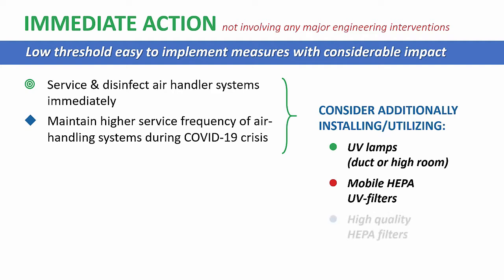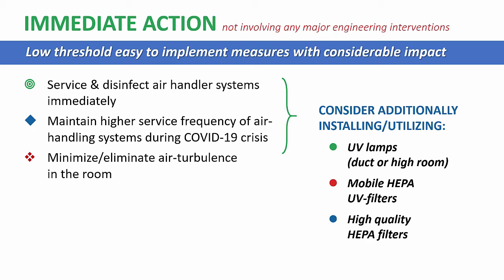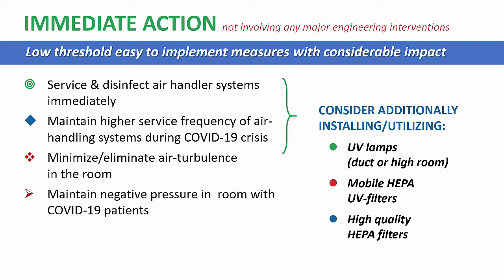And we can also install high quality HEPA filters. These filters we normally install in the supply grills or in the supply duct, to avoid particles to come into the conditioned space. And we can also install them in the return duct to avoid contamination, viruses, bacteria, dust from the living space to go to the air handler again. Another important thing is in rooms with COVID-19 patients to create a laminar flow in the rooms and avoid turbulence as much as possible.